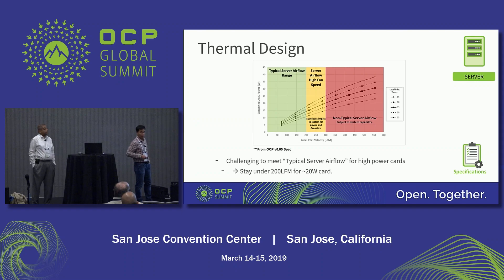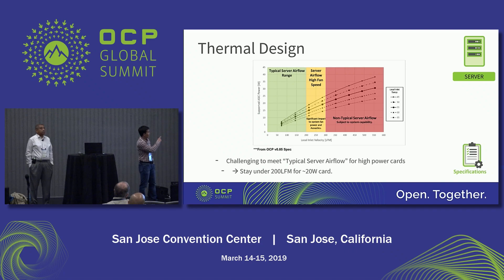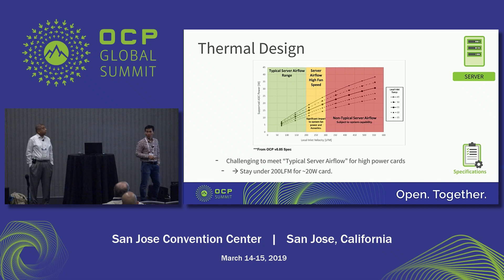For thermal design, this picture from the 0.85 spec shows the different server thermal ranges. From a server perspective there are three ranges, with board power on the vertical axis and airflow on the horizontal. Ideally we want to stay within the typical server airflow range, but we're finding it's very hard to keep cards in the typical server range when they're in the 20-watt-plus range — that's why we need more vent holes.